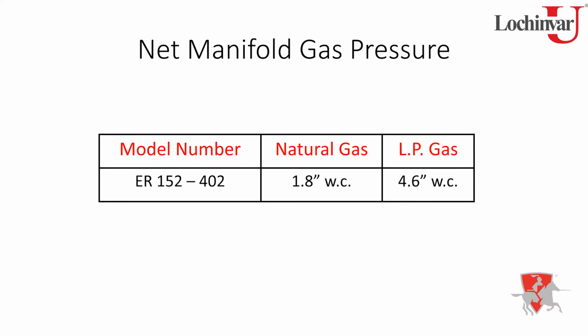So basically, if I'm setting this thing up, I'm going to take the gross manifold pressure by itself and write that number down. Then I'm going to take the air pressure by itself that I've already set and write that number down. And I'm going to subtract the air pressure from my gross manifold pressure, which will give me my net manifold pressure, which is how much gas only I have going into the burners, basically. Yeah, I know it seems like a lot of steps, but it's not that hard.